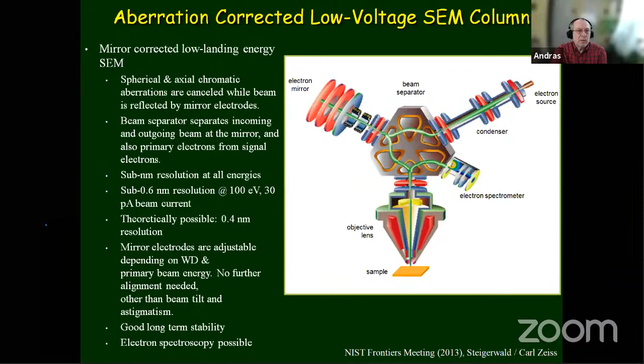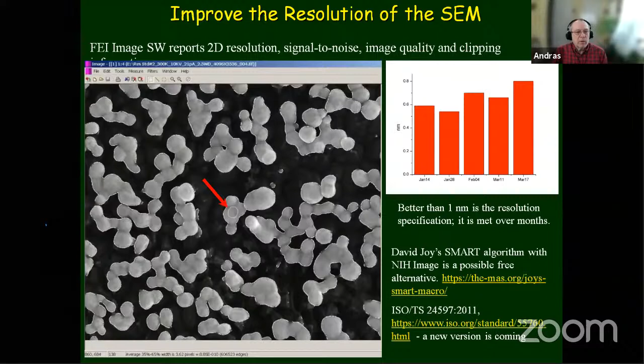Even if you don't have that kind of super duper instrument, but you care about your instrument's performance, if you regularly check it, it will lead to a significant improvement. What you can see here is a software called Image from FEI. FEI users get it. Others can use either this David Joy smart algorithm, or there is one with NIH ImageJ. Then you can download that little macro, or take advantage of the ISO procedure, which is a link here, a new version coming soon. So you can see that these red bar results show what performance you can get from an instrument whose specification is better than 1 nanometer. This is at 15 kV. You can see that significantly better than 1 nanometer resolution is possible. We'll talk a little bit later about how important this is. Next slide, please.